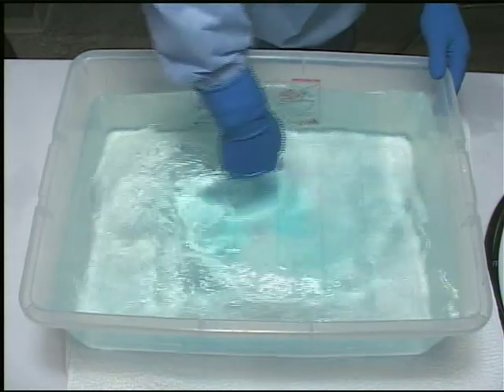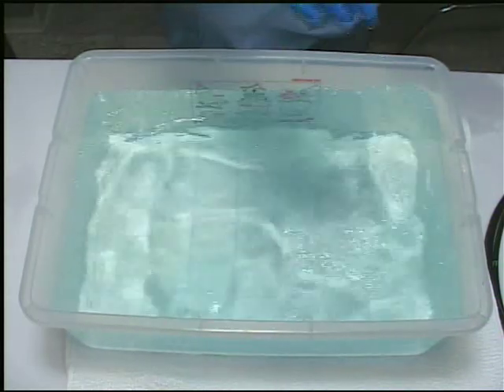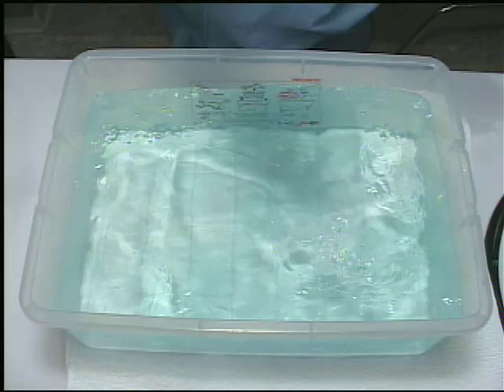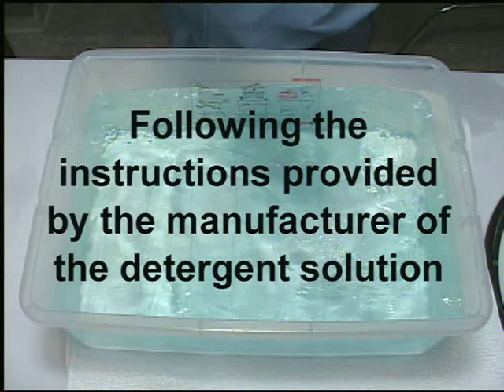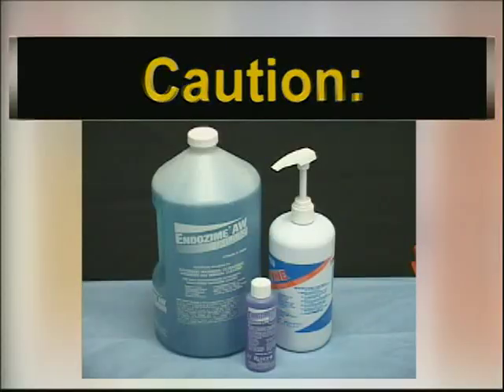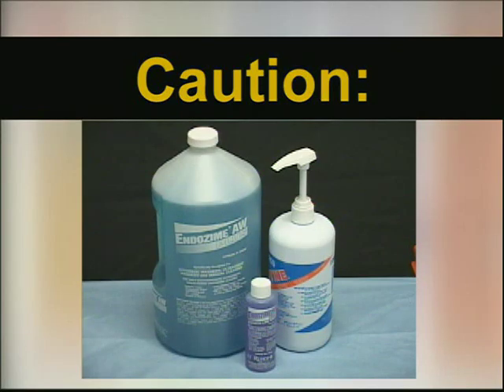After confirming that the endoscope has no leak, prepare a basin of fresh enzymatic detergent solution, following the instructions provided by the manufacturer of the detergent solution. Fresh enzymatic solution should be prepared for each instrument. Caution: the use of an enzymatic detergent immediately after each procedure to dissolve and remove organic contaminants and proteinaceous debris is essential to the care and maintenance of the endoscope from the standpoints of infection control and functionality.